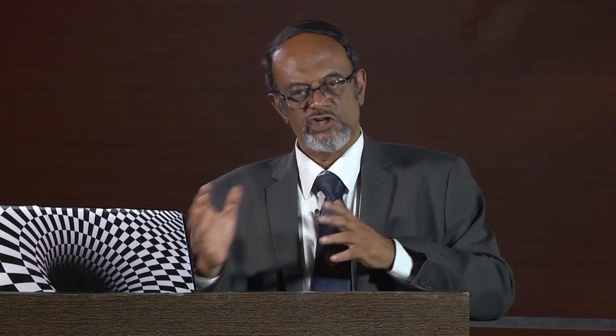Generally, this type of damping torque is given by either air damping, fluid damping, or eddy current damping. In air damping and fluid damping, we have a cylinder with a piston fixed onto the pointer system, and the cylinder chamber is filled either with air or with oil. As the pointer moves, the piston goes in or out of the chamber, acting against the fluid — whether air or liquid — which gets compressed in one direction or the other. The pressure change because of this compression provides the damping. Since this compression happens during both directions of piston movement, the oscillations and overshoots get drastically reduced.